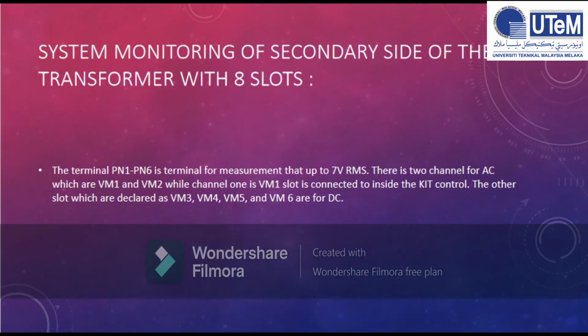Third is system monitoring of secondary side of the transformer with 8 slots. The terminal PN1 until PN6 is terminal for measurement, that up to 7 volt RMS. There is 2 channels for AC, which are VM1 and VM2, while channel 1 is VM1 slot is connected to inside the kit control. The other slot, which are declared as VM3, VM4, VM5 and VM6, are for DC.